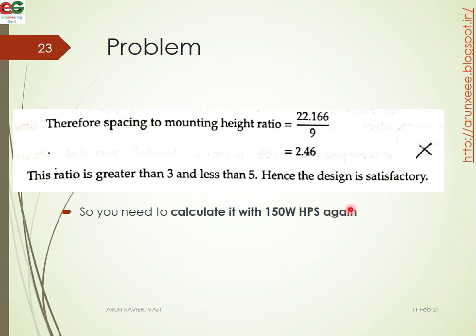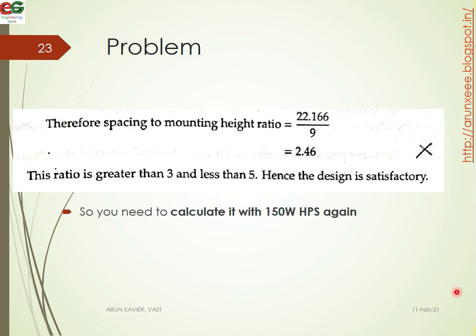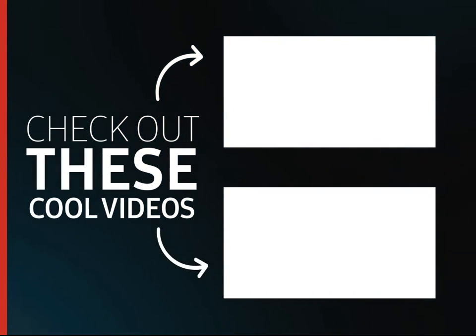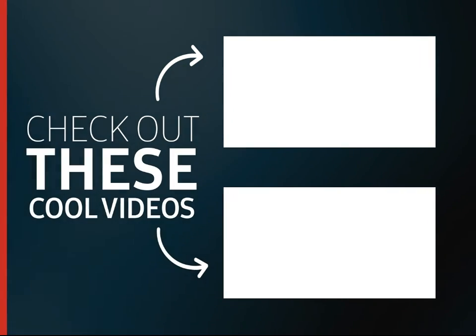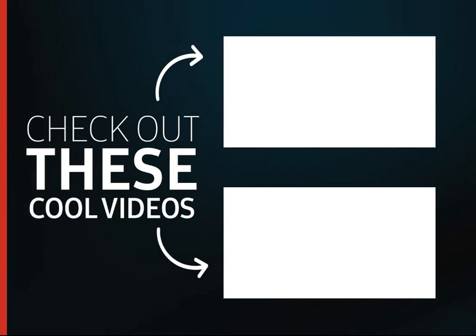We need to recalculate using a 150W HPS lamp and check that the spacing-to-mounting-height ratio falls within 3 to 5. We have checked the road lighting and the different types of lamps that we are using. Please subscribe to the channel and share this video with your friends. Thank you, see you all in my next video with another topic.